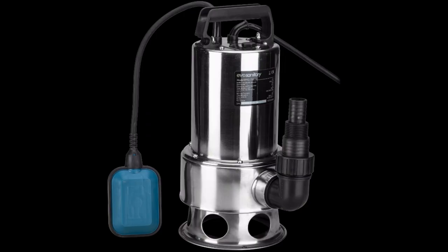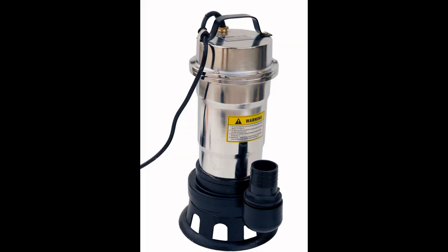For pumping in a straight horizontal line, a pressure of at least 1 bar is required for every 100 meters of pumping. In conclusion, for raising water vertically, for every 10 meters a pressure of at least 1 bar is needed, and for pumping water horizontally, for every 100 meters a pressure of 1 bar is needed. When choosing a pump, we recommend consulting the pump's operation chart to calculate the required flow at the desired distance.